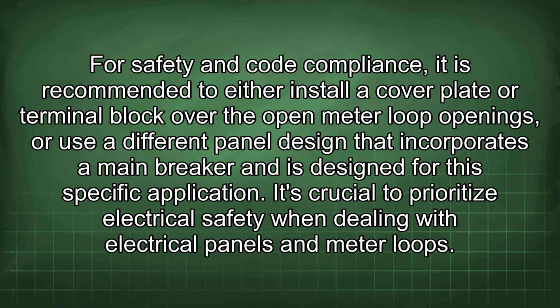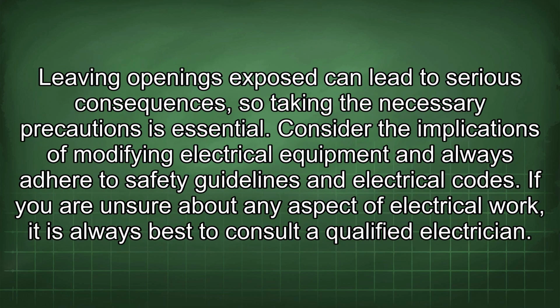For safety and code compliance, it is recommended to either install a cover plate or terminal block over the open meter loop openings, or use a different panel design that incorporates a main breaker and is designed for this specific application. It's crucial to prioritize electrical safety when dealing with electrical panels and meter loops. Leaving openings exposed can lead to serious consequences, so taking the necessary precautions is essential.